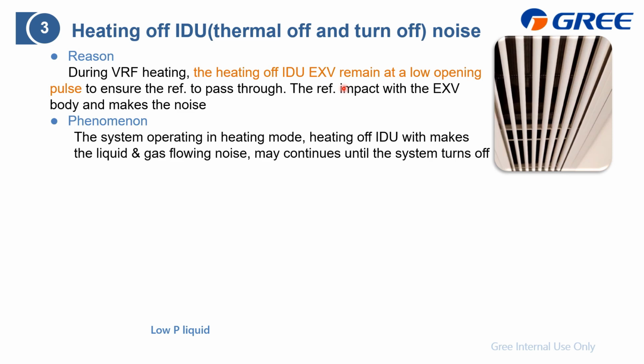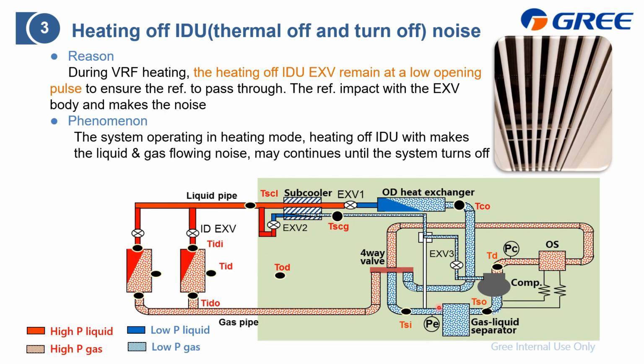However, you need to notice that this is the thermal off or the turn off, which means the indoor room is quiet, especially when you sleep, it will be very quiet, and when this noise happens, it will be annoying. And the reason is that the refrigerant impacts with the EXV body and also makes the noise. So you may wonder why, when the indoor unit is already off, there is still some refrigerant flowing through.